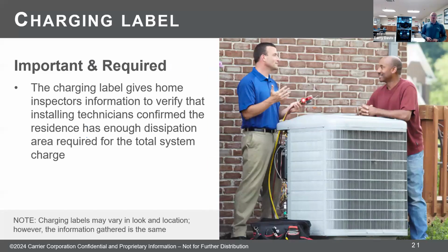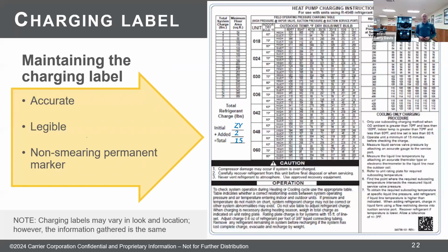That label, to make sure we get the right information on there, for areas where you have home inspections, that lets the home inspector know how much refrigerant is in that system, so they can verify there's enough dissipation area for the total system charge. Okay, so that's what we're talking about here. You'll write that in a permanent, non-smearing marker, where it can actually be read. For me, if you ask my kids, they'll say they'll have to have somebody else write it for me. Just write it as legibly as possible inside that label. That's on the inside of the cover, so that when you put that cover back on, it's protected from the weather and should stay legible. If you're out servicing that unit and you see that it's wearing or fading, rewrite it and darken it in there.